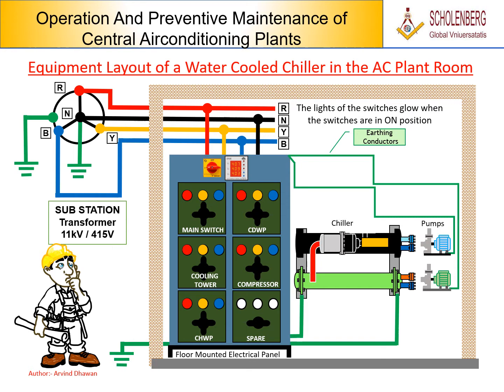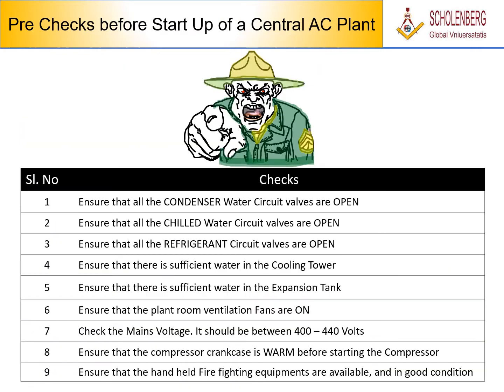This is the equipment layout of a water-cooled chiller, in the AC plant room. Pre-checks before startup of a central AC plant. Serial number. Checks. 1. Ensure that all the condenser water circuit valves are open. 2. Ensure that all the chilled water circuit valves are open. 3. Ensure that all the refrigerant circuit valves are open. 4. Ensure that there is sufficient water in the cooling tower. 5. Ensure that there is sufficient water in the expansion tank.